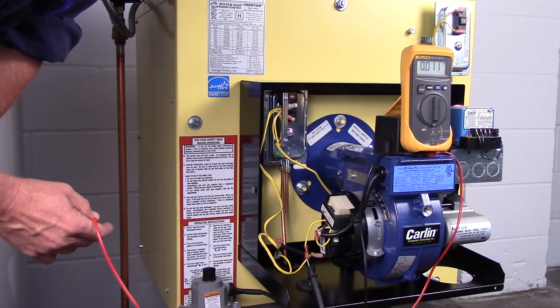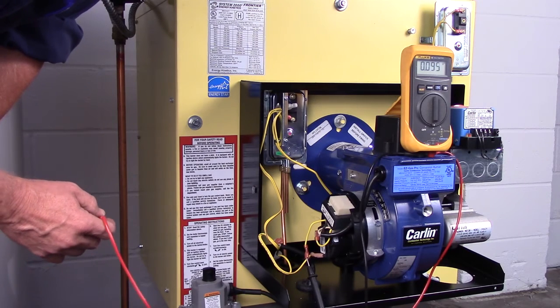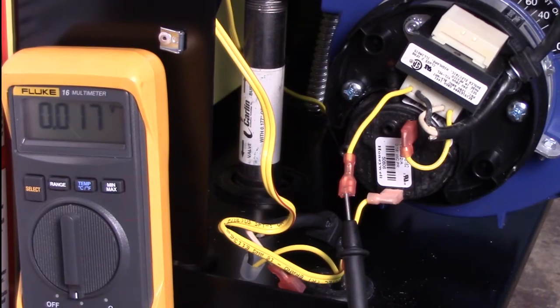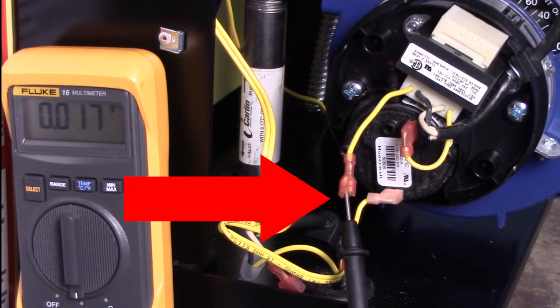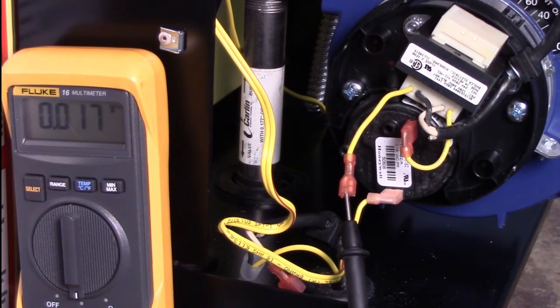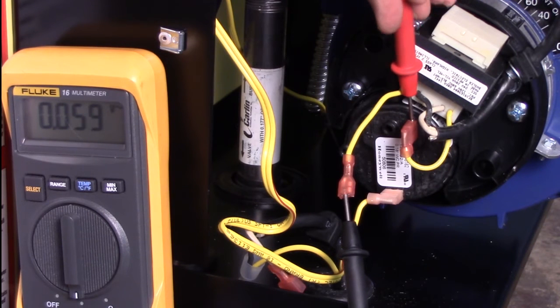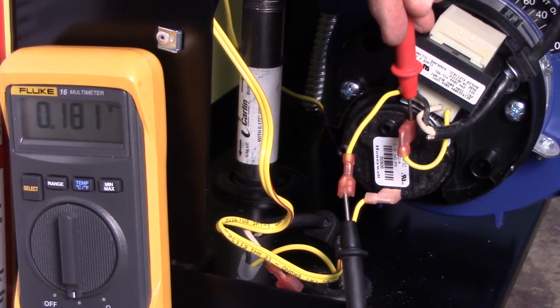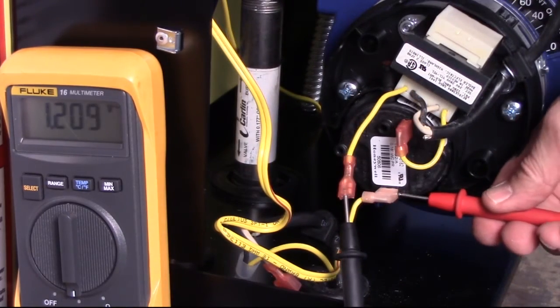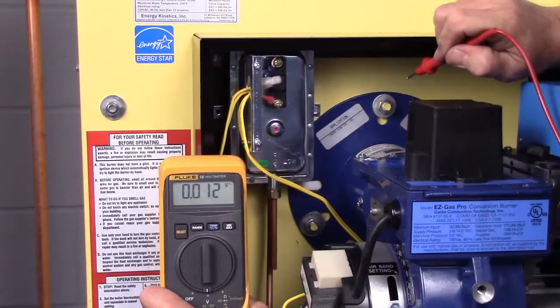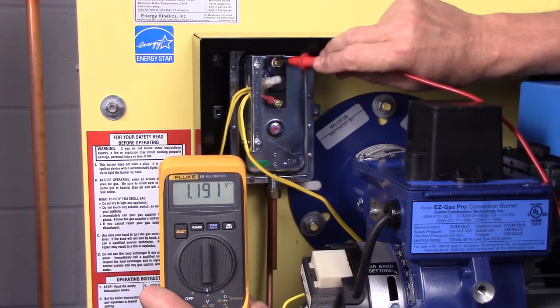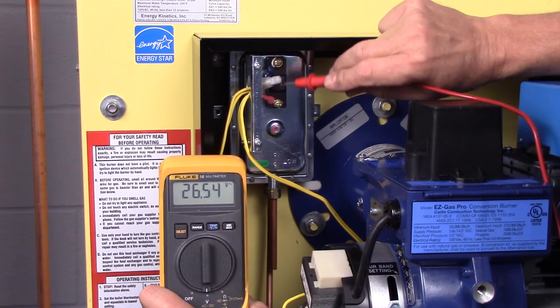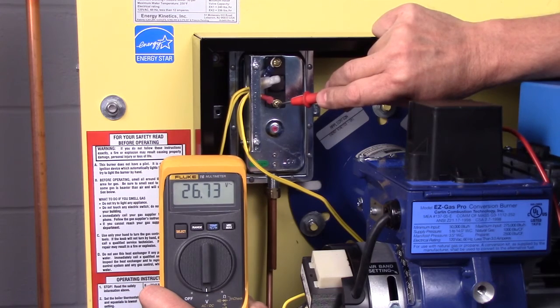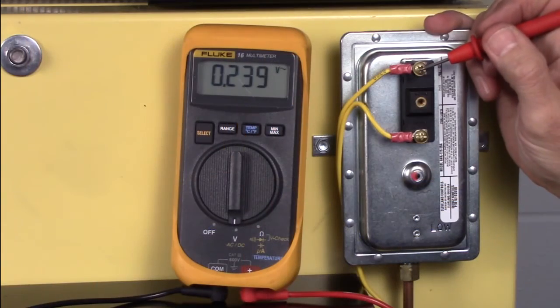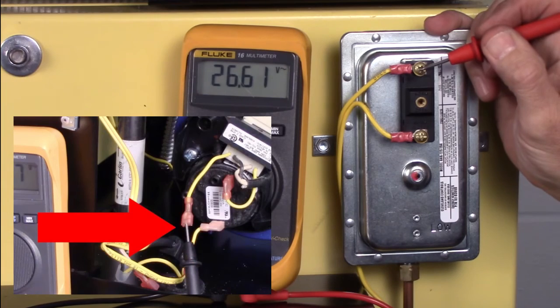You can accomplish this by disconnecting the gas valve lead from the transformer and inserting a voltmeter test lead directly into the transformer lead. Then touch the other lead to each terminal in succession through each safety switch in series as shown. Trace the circuit by touching a voltmeter test lead to each switch terminal with the other voltmeter test lead on the transformer lead.